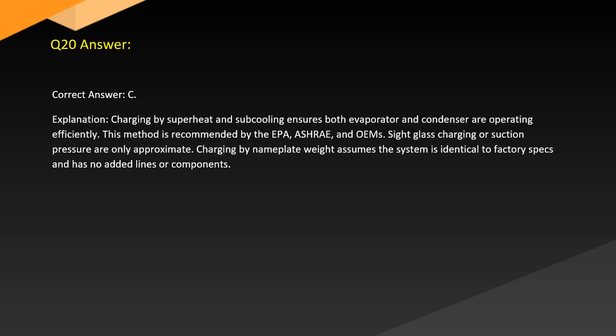Answer. Correct answer. C. Explanation. Charging by superheat and subcooling ensures both evaporator and condenser are operating efficiently. This method is recommended by the EPA, ASHRAE, and OEMs. Sight glass charging or suction pressure are only approximate. Charging by nameplate weight assumes the system is identical to factory specs and has no added lines or components.